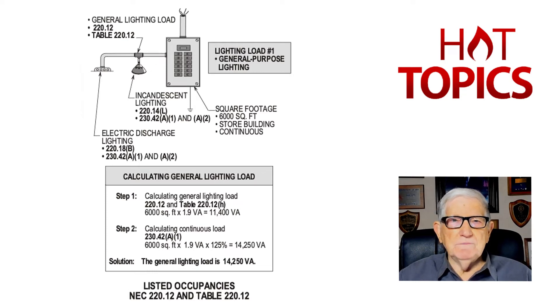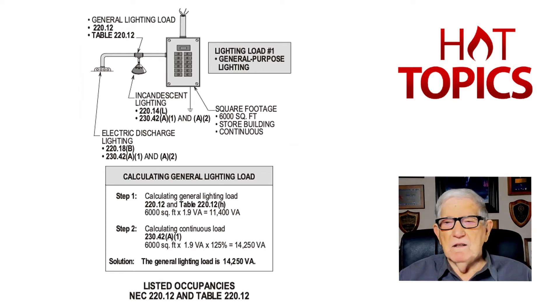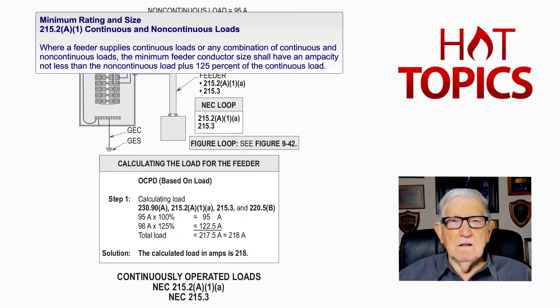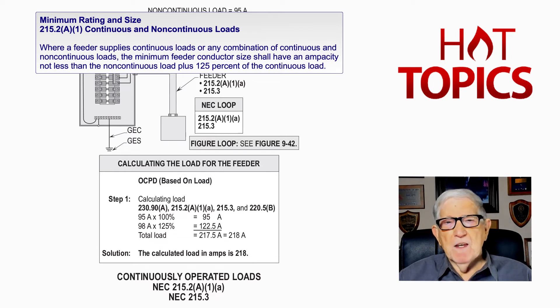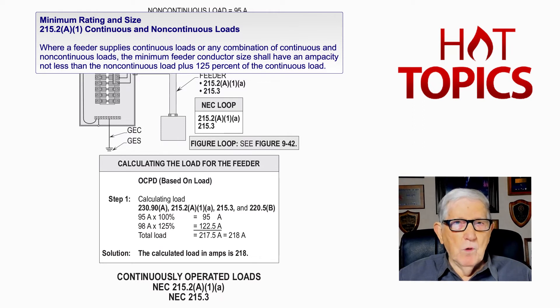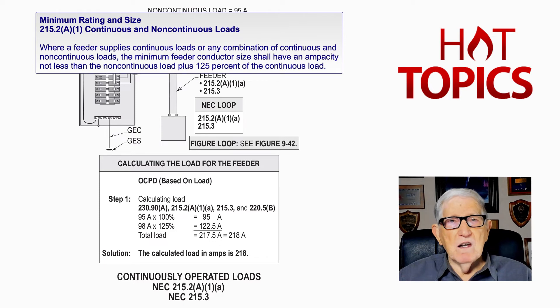As you can see, that is the problem of interpretation. Not knocking anybody's interpretation — I'm just saying everyone doesn't look at this the same. Now let's look at 215.2a1 in the 2023 edition — that would be 215.2a1a in the 2020 edition. Notice how it reads: where a feeder supplies continuous loads or any combination of continuous and non-continuous loads, the minimum feeder conductor size shall have an ampacity not less than the non-continuous load plus 125% of the continuous load. Going back to table 220.42a1 in the 2023 edition, the 125% rule you see here — some people say it is included, some people say no.